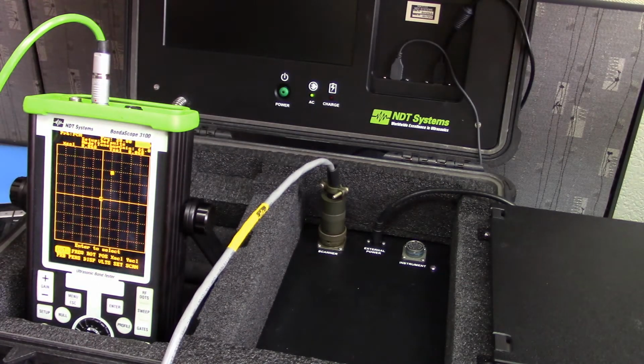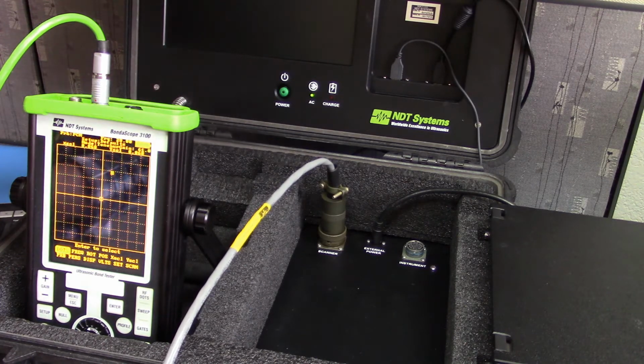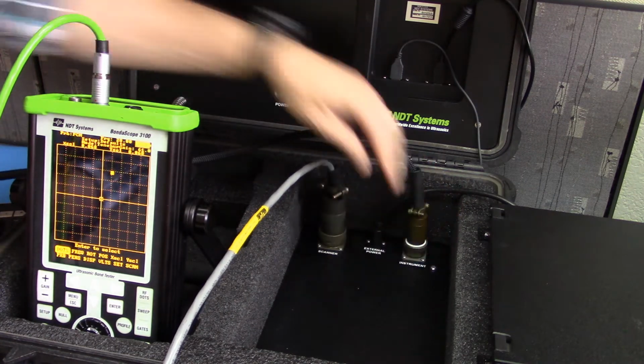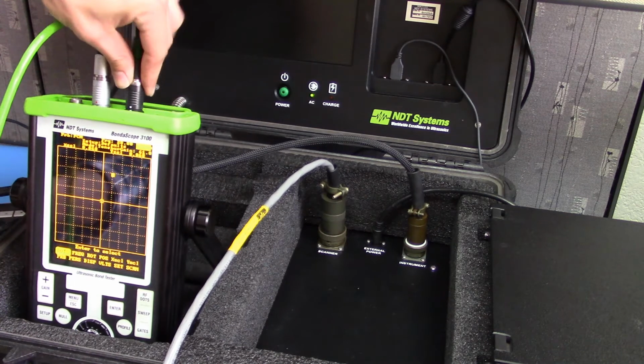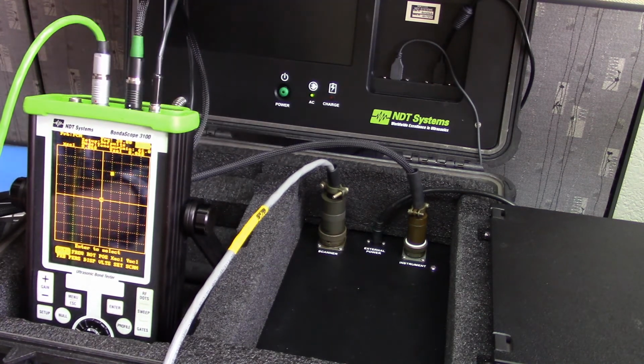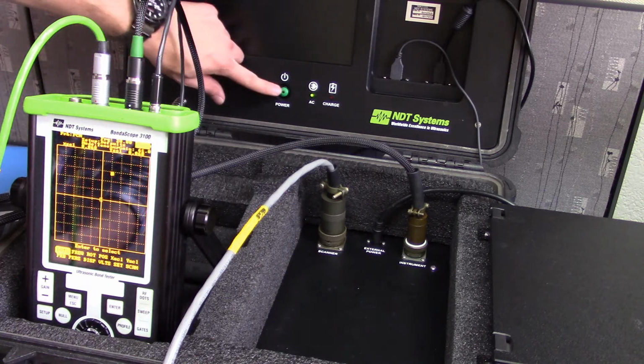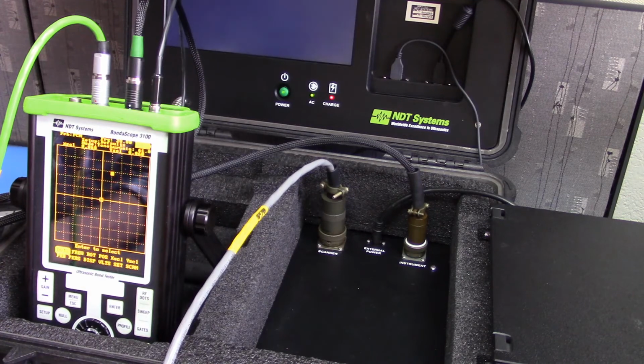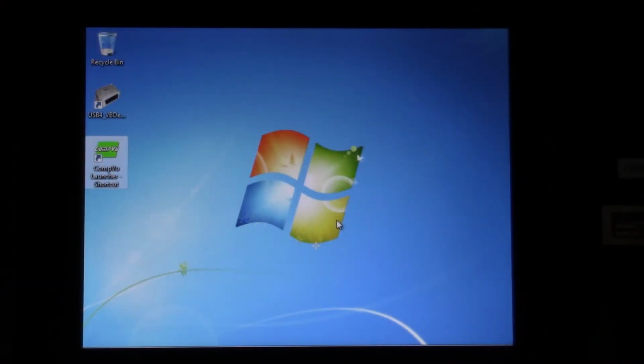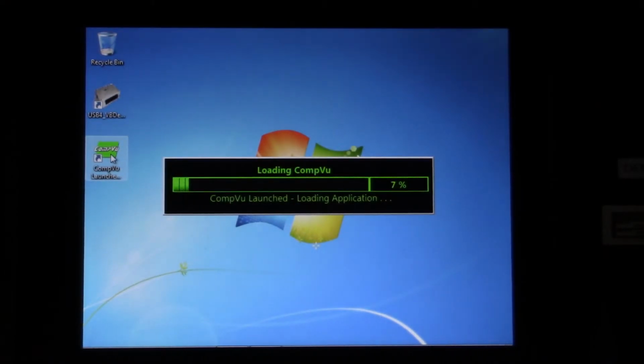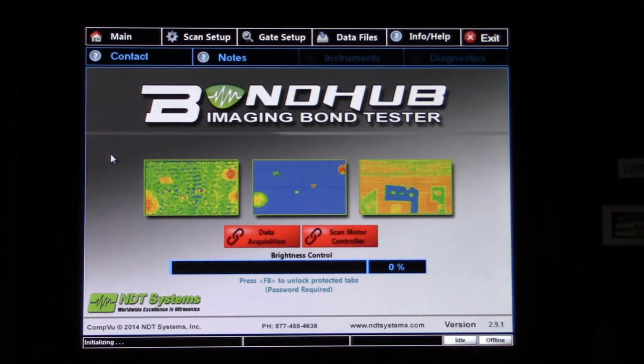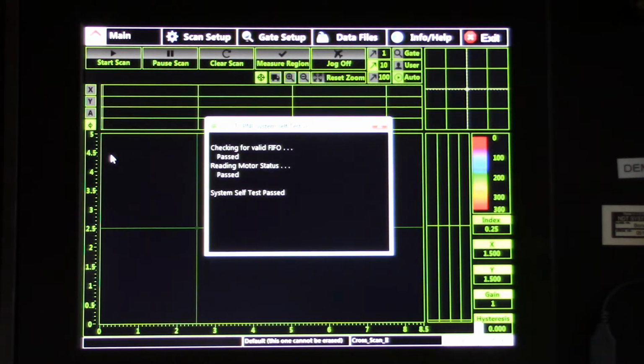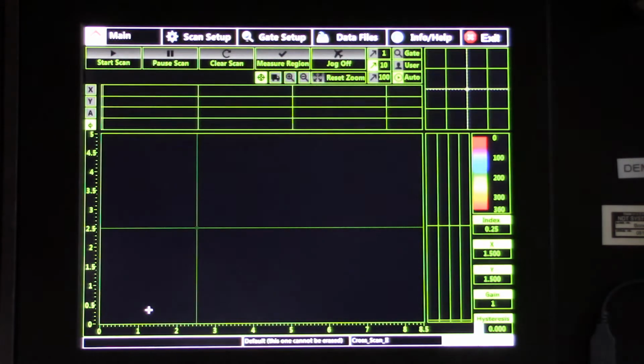Then go ahead and connect the bond tester itself to the BondHub. Once all those cables are connected, turn on the BondHub itself. Once the scanner and bond tester have been connected to the BondHub and the BondHub has fully booted up, go ahead and open the CompView software. Once the system self-test has passed, close the window and go to Scan Setup.